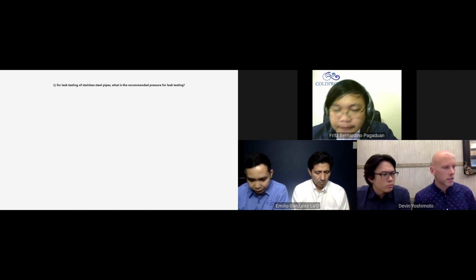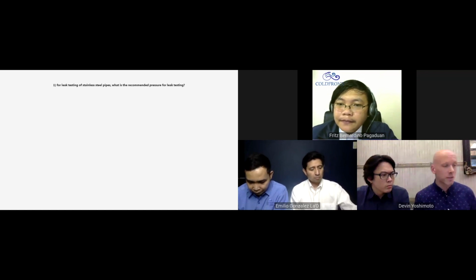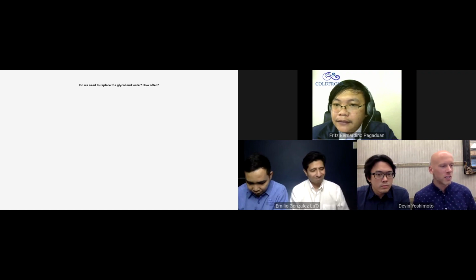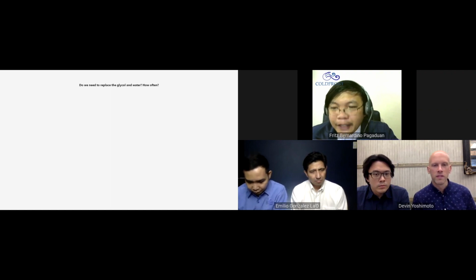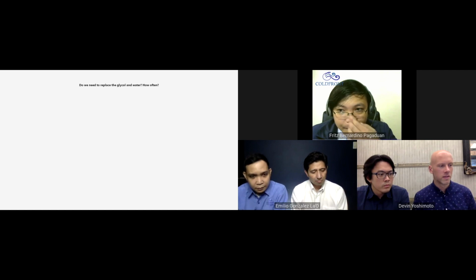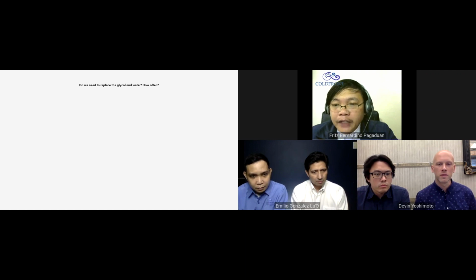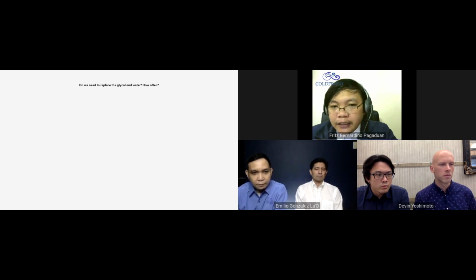Excellent. Thank you very much. We have a couple more questions, including from the Royal Duty Free shops. The question is, do we need to replace the glycol and water? How often? Actually, based on our previous projects, we didn't replace glycol and water as long as there's no contamination inside and no leaks. The only maintenance for this system is the cleaning of the Y strainers, because you cannot flush that 100%. Sometimes we add maybe around 2 gallons for purging of air bubbles in the system.